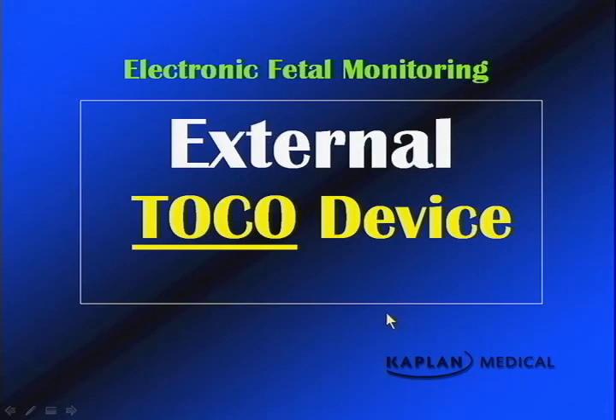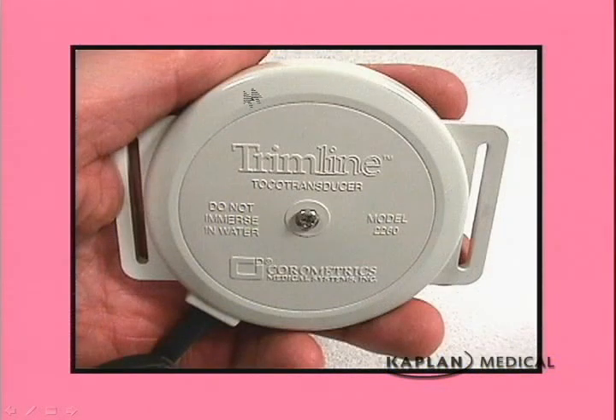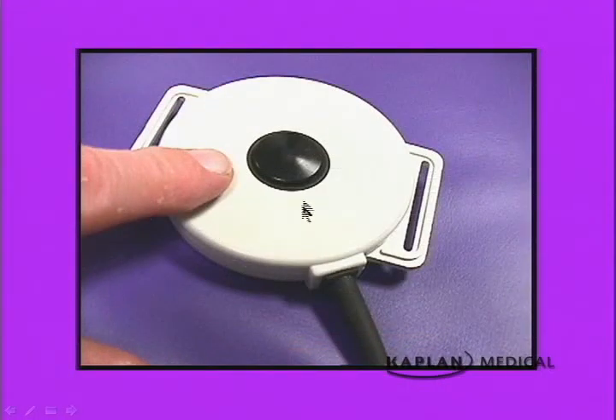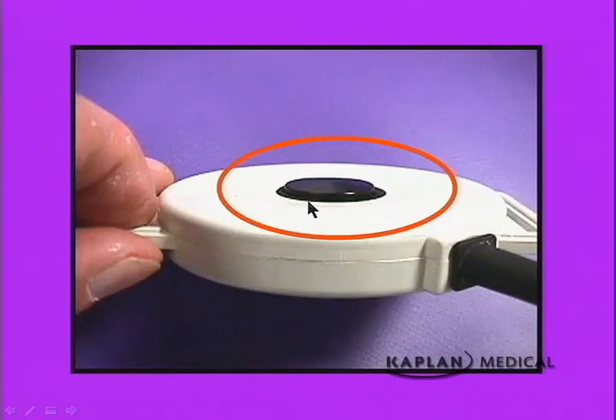So we've got to assess if there are contractions. How do we do that? We use this external tocotransducer. The business end is over here. It has this button which pushes out. It is spring-loaded. You put this on the mother's abdomen. It pushes in the mother's abdomen.